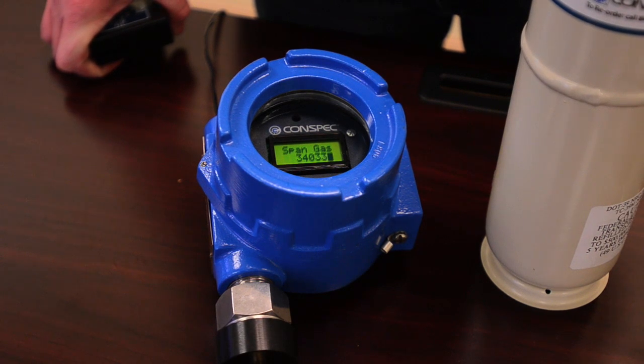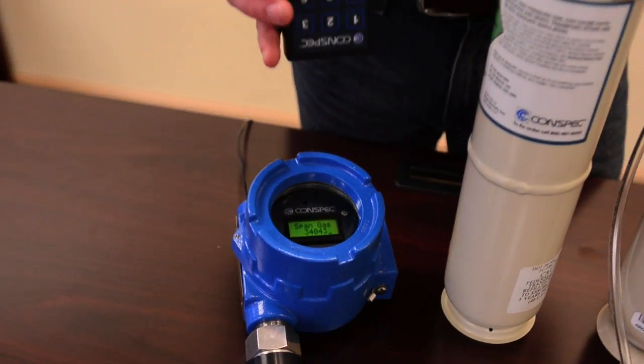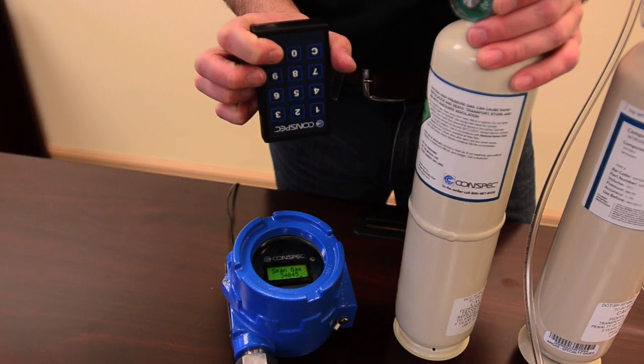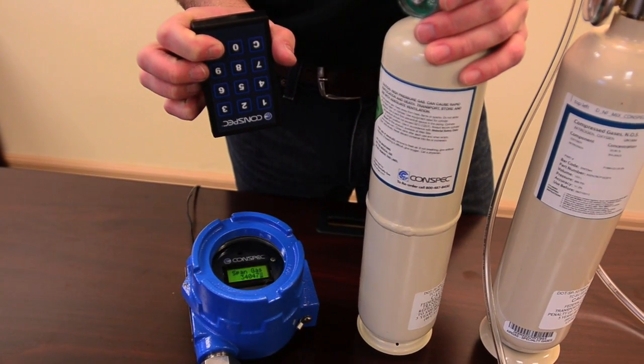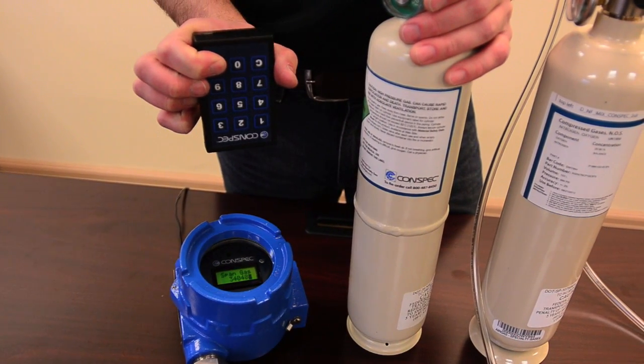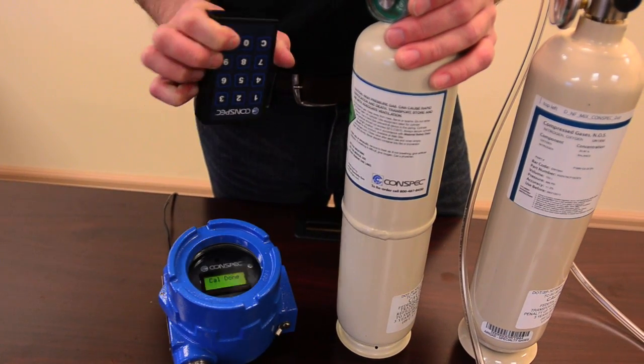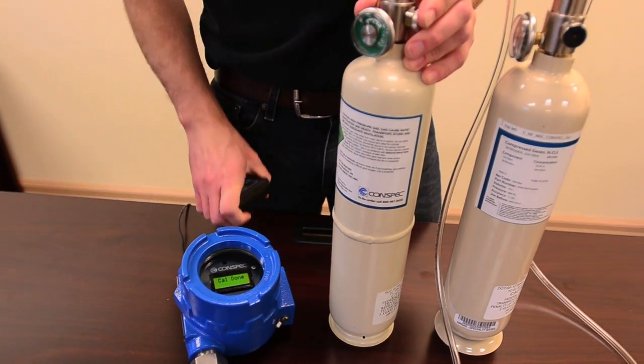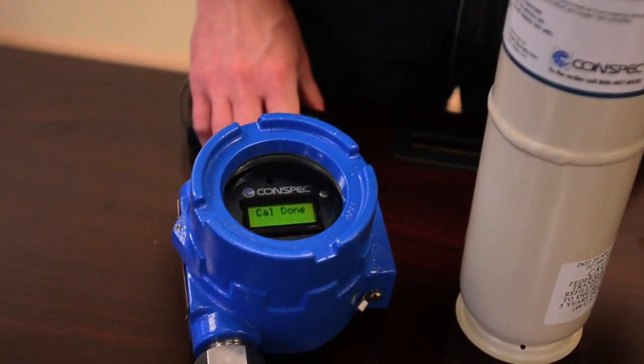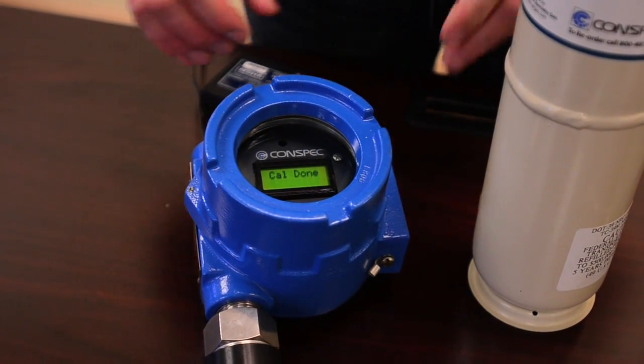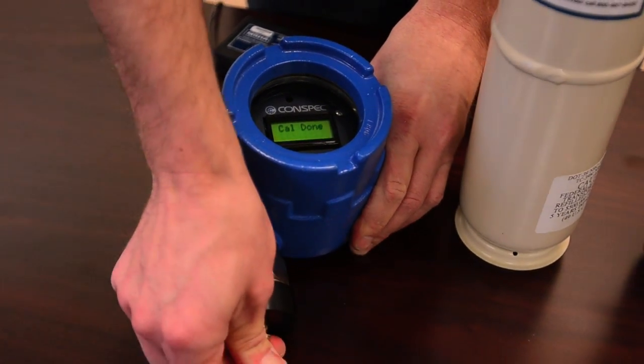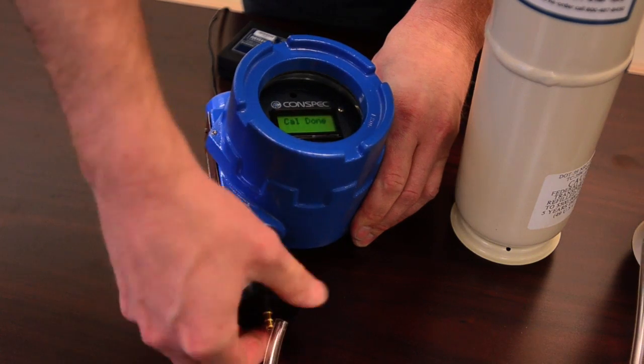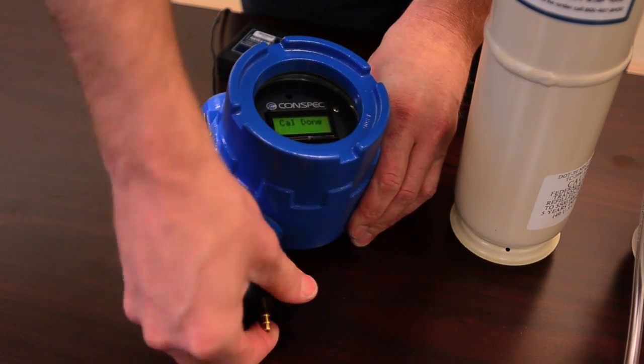This value that we're seeing here is a pretty good value for a 0 to 100% LEL. Looks fairly stable. It is increasing. For the sake of calibration, we can enter this value. We could let the gas stay on for another minute or so to get a higher reading, but this looks pretty good. So now we see the cal done message. We can shut our gas off, and we want to disconnect the calibration adapter to get fresh air into the sensor to allow it to recover.